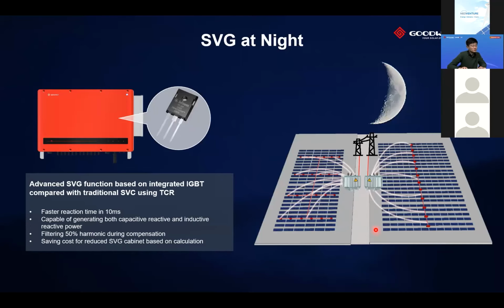SVG is a very important and critical issue. Before GoodWe HT products were invented, C&I projects normally needed to invest in an SVG cabinet. But at GoodWe, we integrate this SVG function into the inverters. With this high integration design, it is capable of generating both capacitive and inductive reactive power at night, and it saves cost for sure.